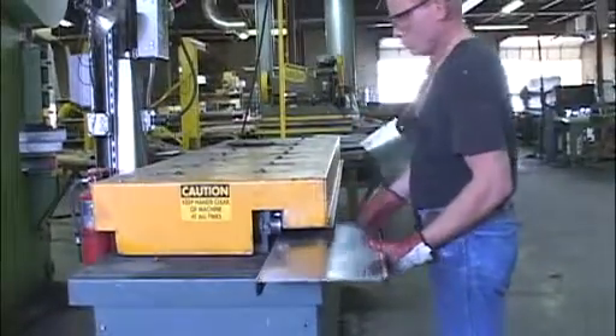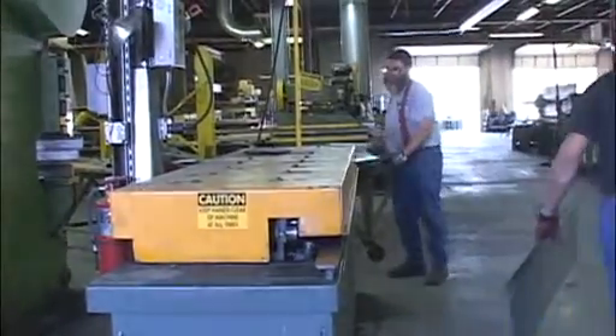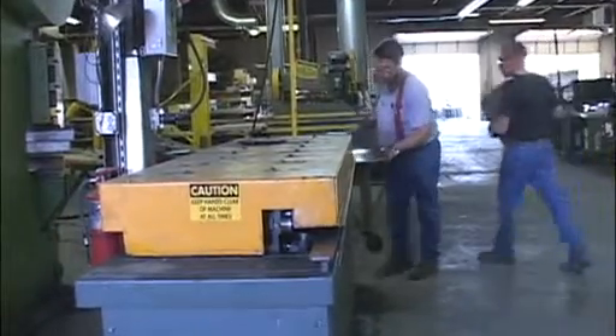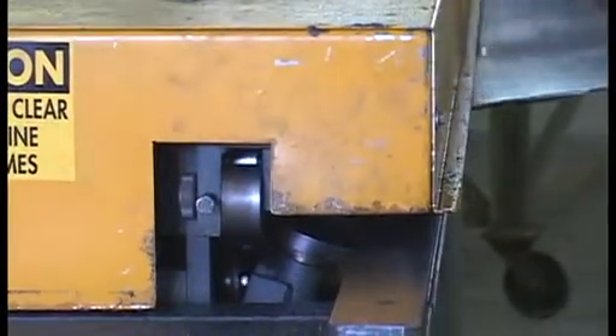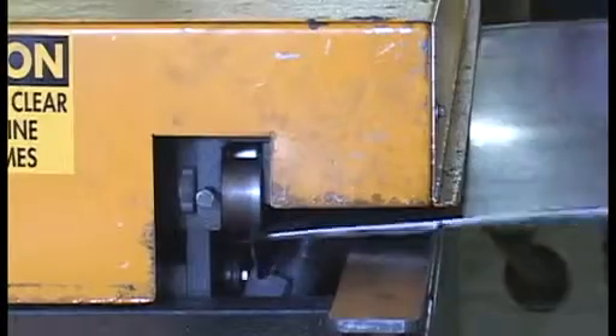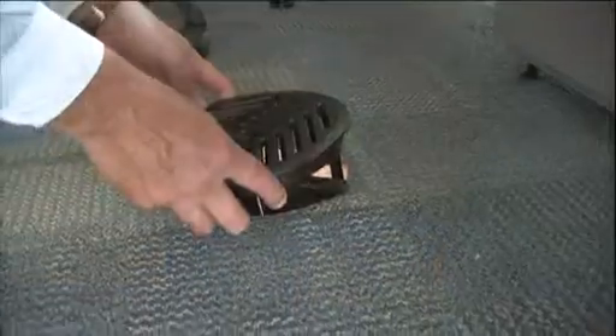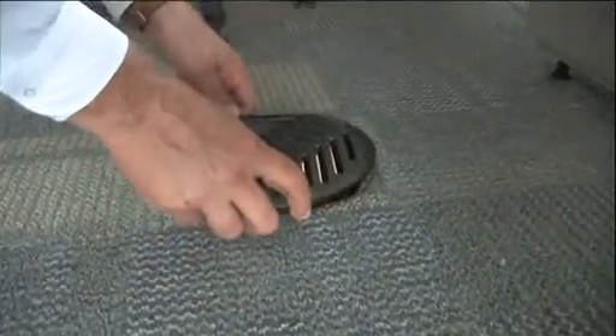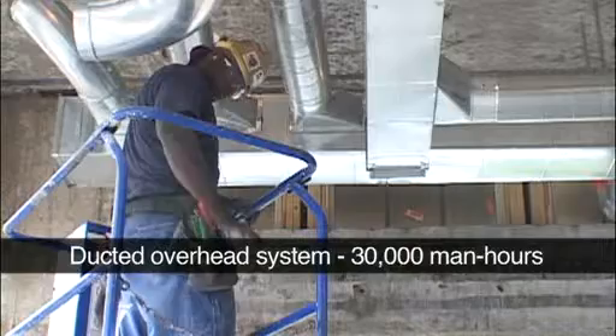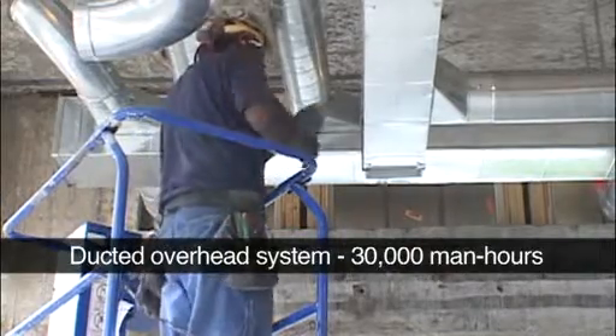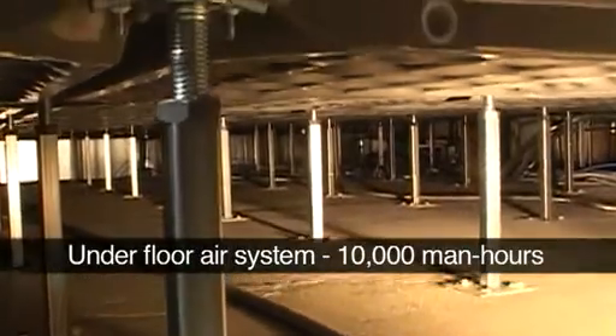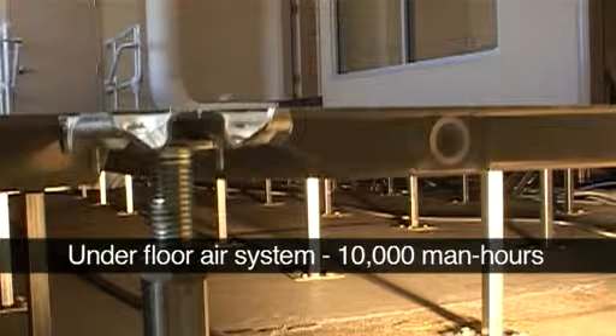As you can imagine, there are substantial savings to be found regarding ductwork costs. The material and labor to fabricate the ductwork in overhead mixing systems is considerable. On-site, underfloor air delivers efficiencies. Experience has shown that a 300,000 square foot building with a ducted overhead system can require as much as 30,000 man-hours of field labor. The same size building using underfloor air can be as little as 10,000 man-hours of field labor.